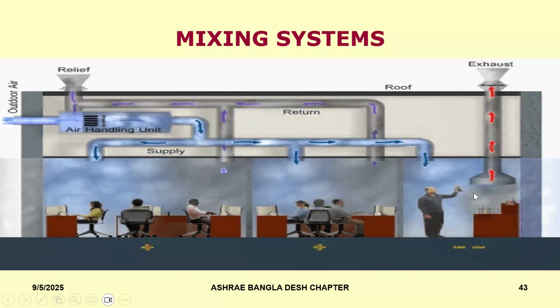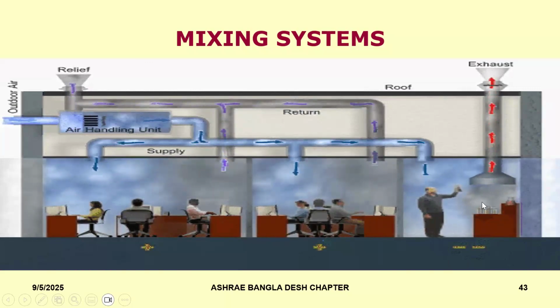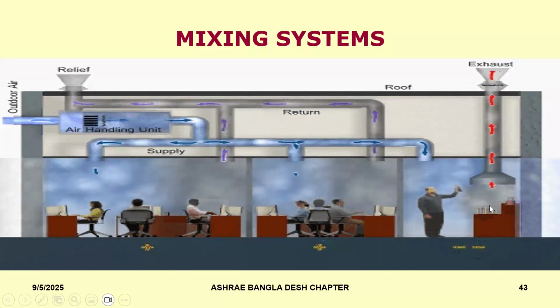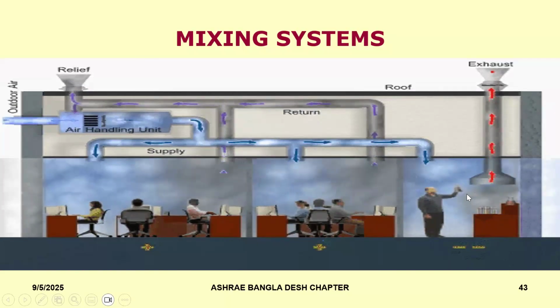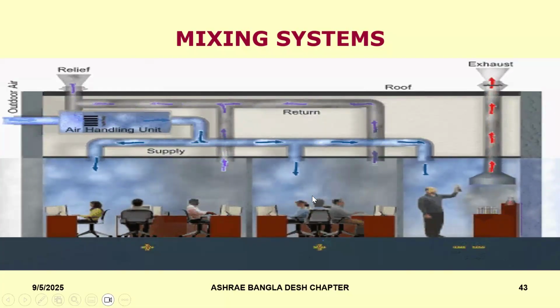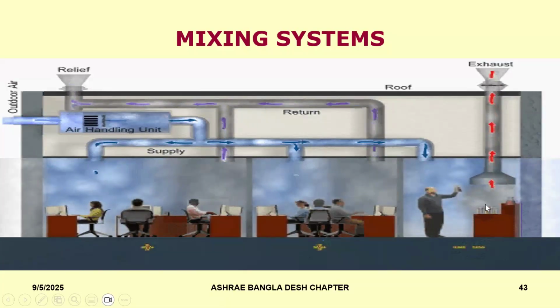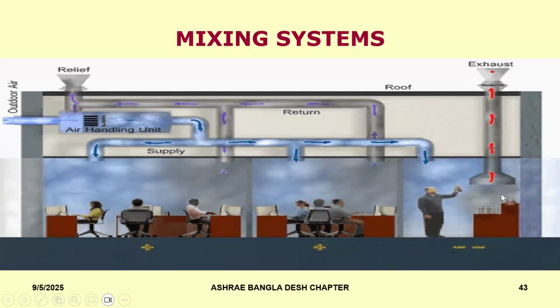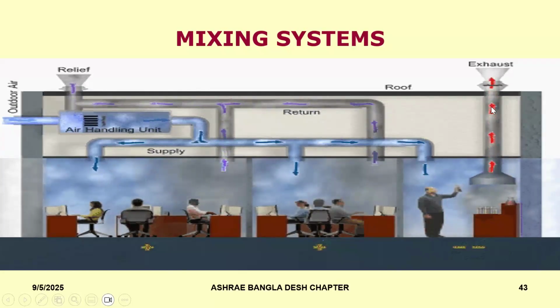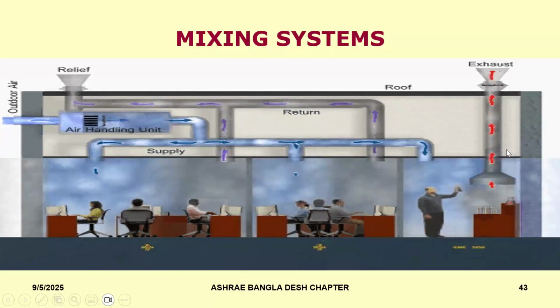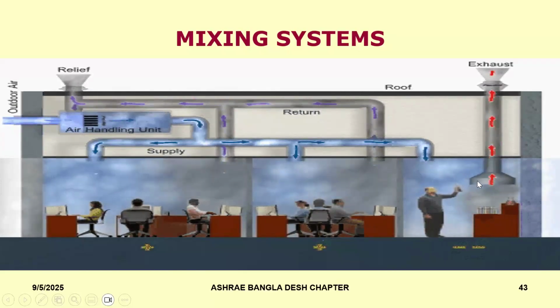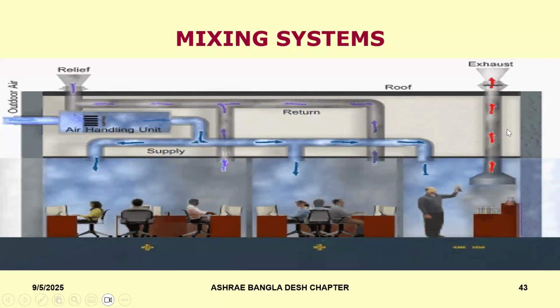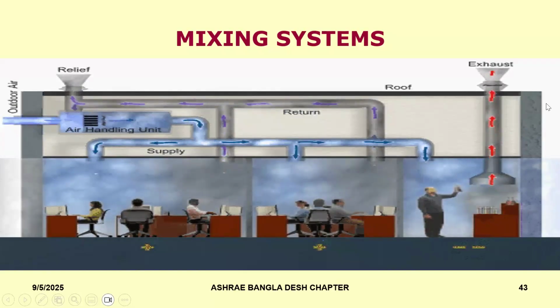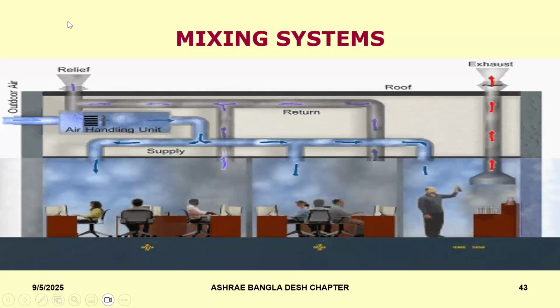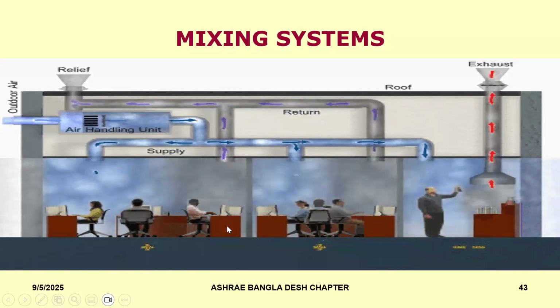Now, in this last room, obviously, there is a lab. Some kind of experiments are going on that is releasing some fumes. Now, you don't want this fume to come back into these spaces. So what you do here is that you're making sure that this area remains under negative pressure and all these fumes are exhausted out. Now, whatever is being exhausted out, that's the air coming into this space, that needs to be compensated. So that compensation happens via the relief air here and the outdoor air here.